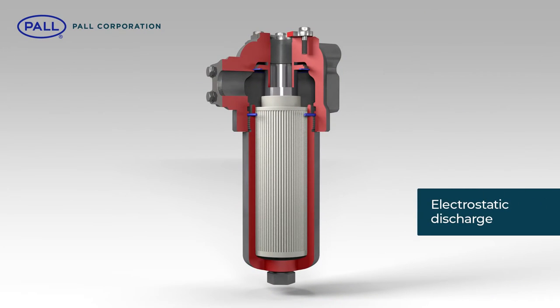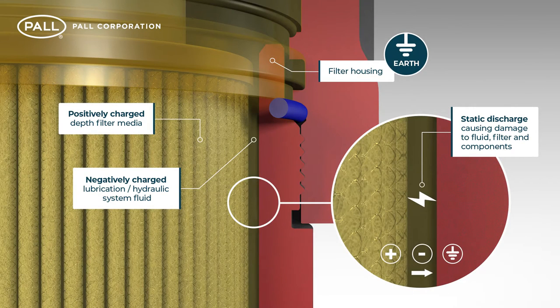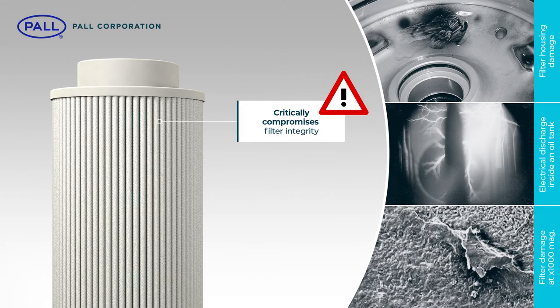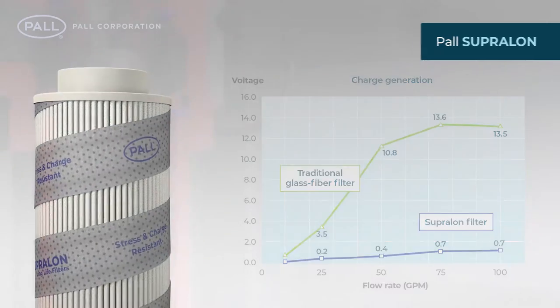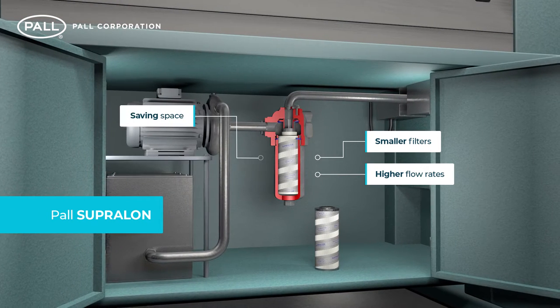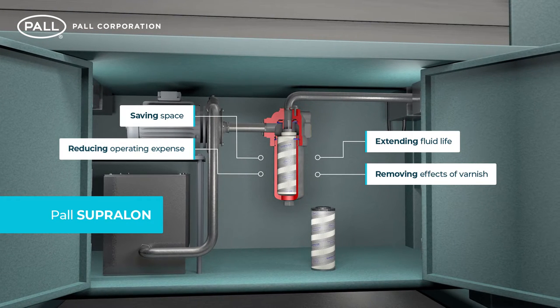Frictional contact between fluid and filter media results in an electrostatic charge. If not dissipated, this accumulates and discharges via the filter housing, often blasting holes through the filter media and damaging components. This critically compromises filter integrity and causes fluid degradation and potential varnish formation. Pall Supralon filters incorporate a conductive spiral wrap that continually dissipates static charge, preventing buildup and any high-voltage arcing. The consequence is smaller filters with higher flow rates can be confidently incorporated into hydraulic and lube systems, saving space, reducing operating expense, extending fluid life and removing the detrimental effects of varnish.